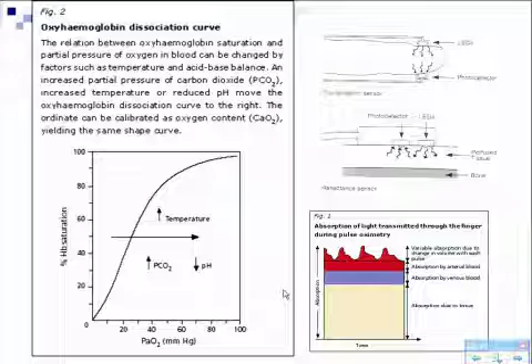This is the actual transducer. This is what we normally think of out of pulse oximetry, and this one is the actual reflectance, where the photodetector is right next to the LED. So the LED fires the two lights, and then it reflects off the cranium, usually off the bone. In kids, it's pretty easy to do because the distance between the skin and the bone is small. The bad thing about this is an LED, which is a light-emitting diode, which produces heat. So in kids, you'll get burns. You get circular burns if you don't change these out every once in a while. You've got to move it around. We used to do this a lot in preemies, and you had to be really, really careful. About every 2 hours, we switched out where the reflectance pulse oximeter was.